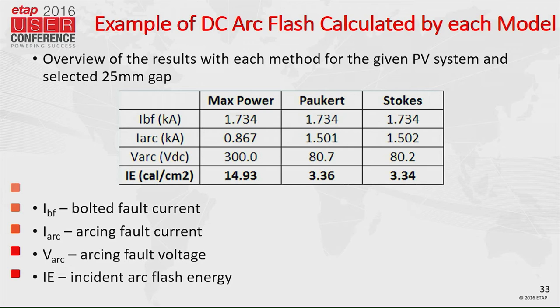Now, if you went back to that graph I showed you earlier, with that sinusoidal shape for the power transferred to the arc, and you looked at a current of 85%, you would find that we would expect to see about 45% of the maximum power actually delivered to the arc in that situation. And here I'm showing you a little bit less than 25% incident energy. Why is that? I'll tell you in a minute.